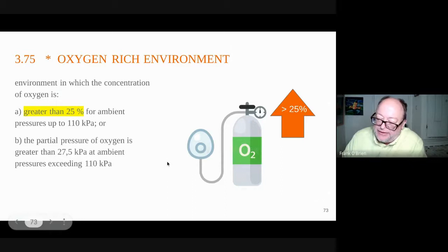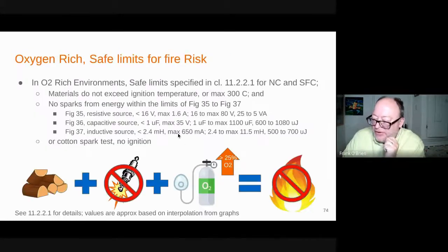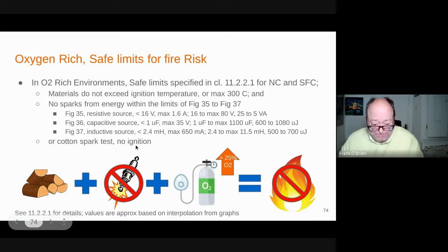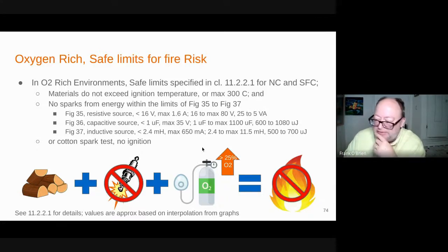Last but not least, oxygen rich. The idea is if you go over 25%, things will burn better. And so once they burn better, ideally we'd want to limit the ignition source. So there's some curves, figures 35 through 37, that talk about energy that we could limit things to. And these are the ranges, depending on resistive, capacitive, inductive energy. And there's a cotton spark test at the end of the day if we don't meet these curves.